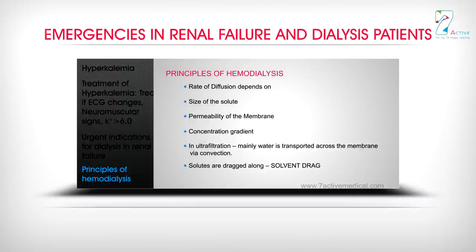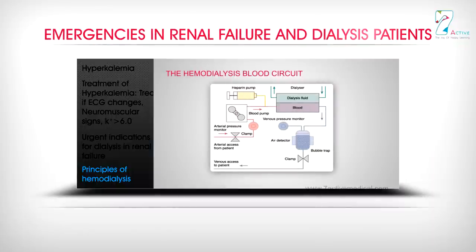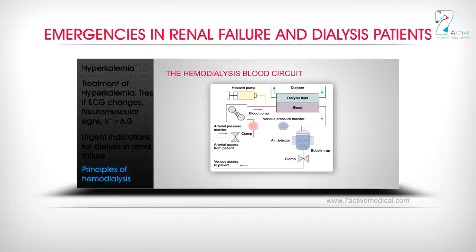In ultrafiltration, mainly water is transported across the membrane via convection, and solutes are dragged along (solvent drag). The hemodialysis blood circuit includes: dialyzer, dialysis fluid, blood, heparin pump, blood pump, clamps, arterial pressure monitor, arterial access from patient, venous pressure monitor, air detector, bubble trap, and venous access to patient.